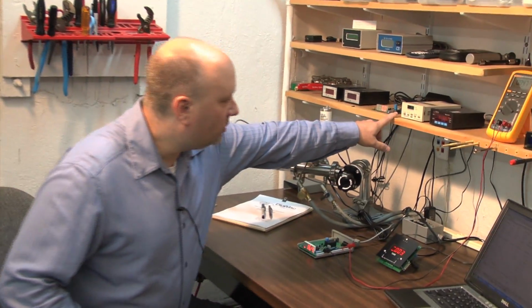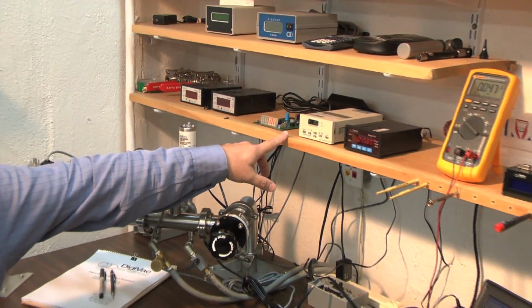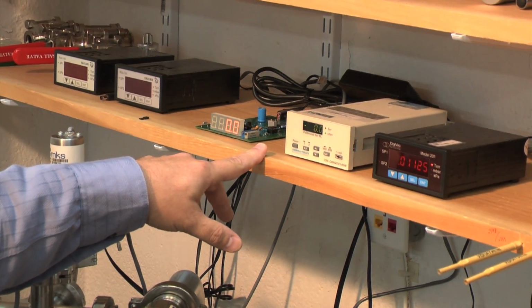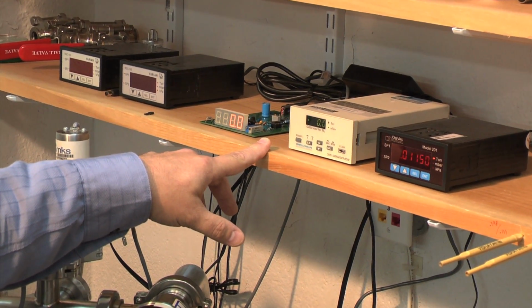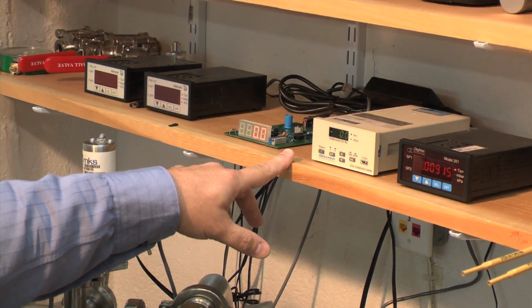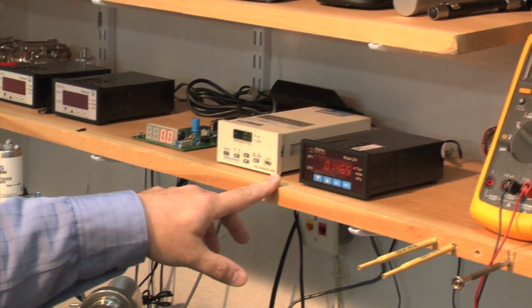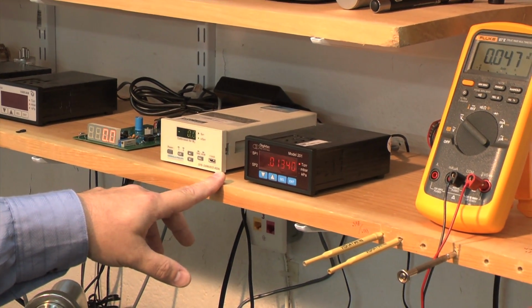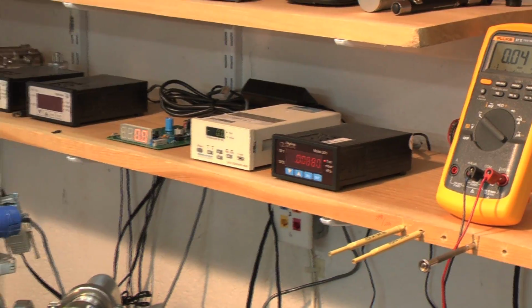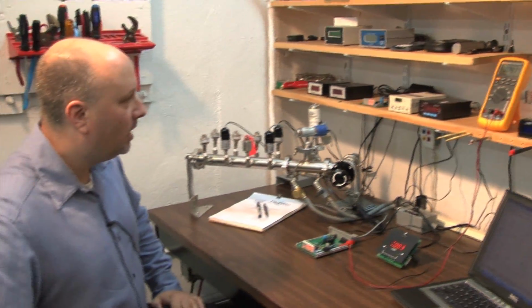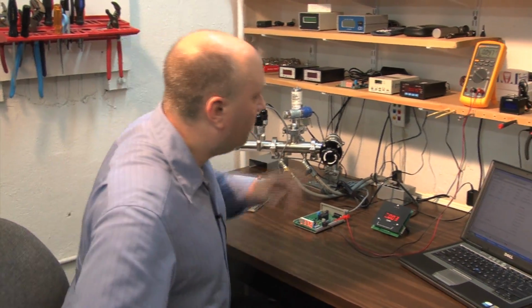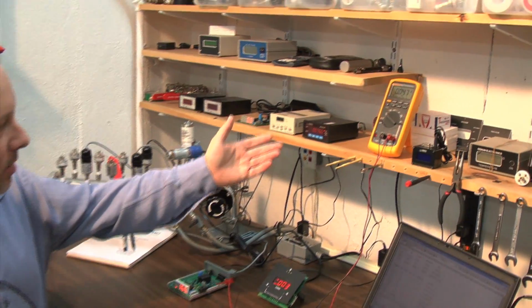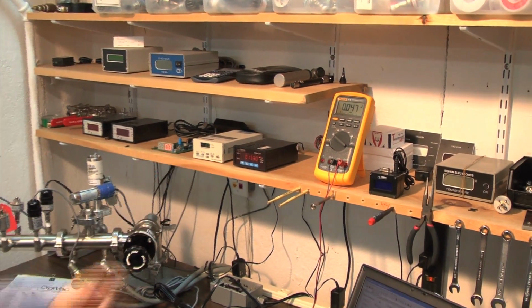My convectron gauge is an ultra-low vacuum gauge. It's good down to 10 to the negative third. We use this for readings between 10 to the negative third and 1 torr. Our Baratron gauge is used for readings from 1 torr up to atmosphere, generally presumed to be about 760 torr on any given day. And of course, our third instrument we use is a voltmeter. It's a common voltmeter, but it's been calibrated to a NIST traceable standard.